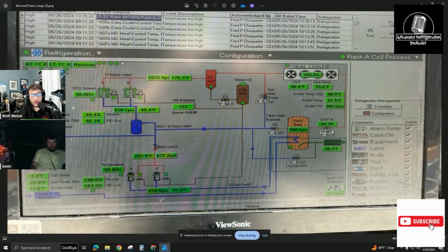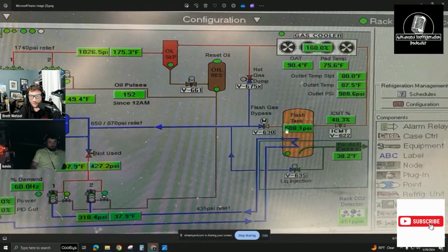That's weird. Yes. That one looks beautiful right now. The what looks beautiful? It looks beautiful right now, like at 508. And actually, I think this pressure was maintaining right at 520, but he had it set in the controller for 530. Like I said, I know this is off because we verified the 326, and he verified it when he replaced it to make sure it was reading right. And this is reading about 10 pounds off. So, hey, this is an older rack, it could be reading a little farther off. But everything else looked great.